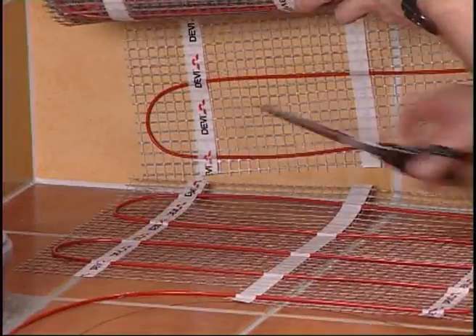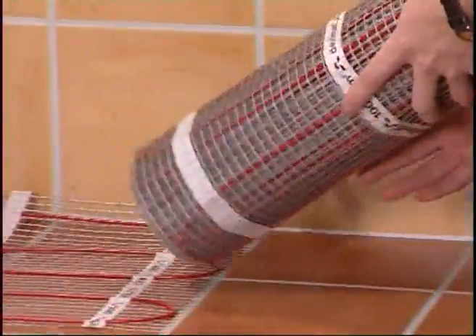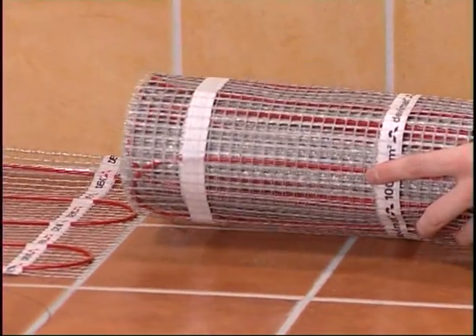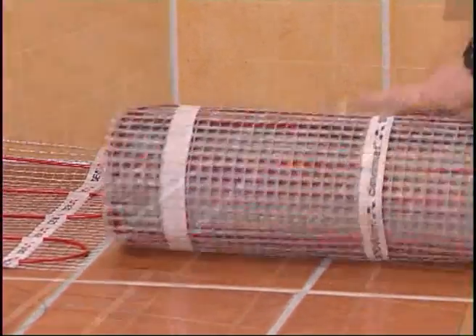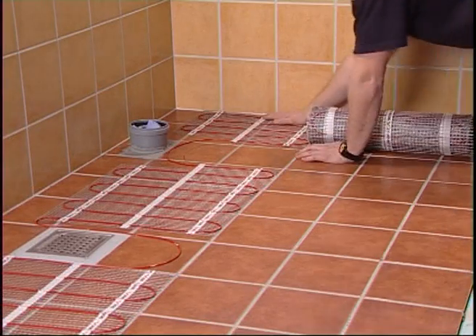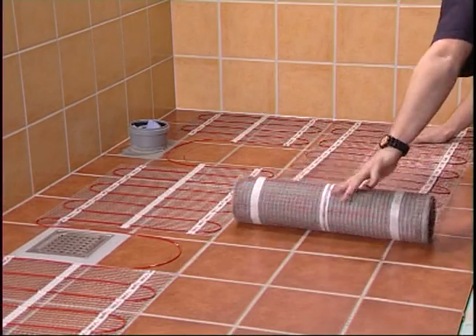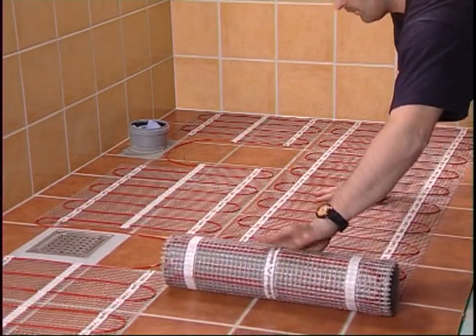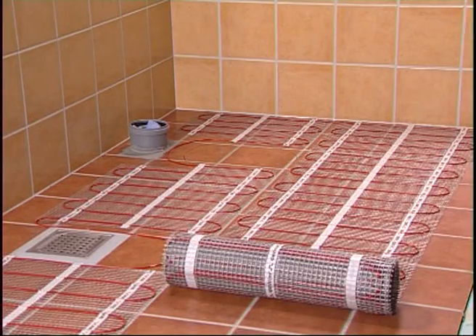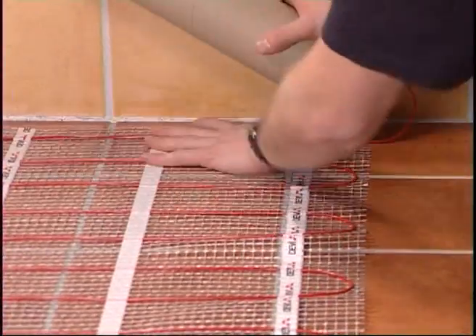When you reach the wall, cut the grey mesh of the mat and turn it in the desired direction. Do not cut the red cable. The heating mat must not be shortened. You might like to test how you want to lay the DEVI heating mat — adjust it so you get the optimum distribution. The self-adhesive effect can withstand 10 to 20 adjustments, so you can move the mat several times until the adhesive effect reduces. Remember, the heating mat must not be shortened.